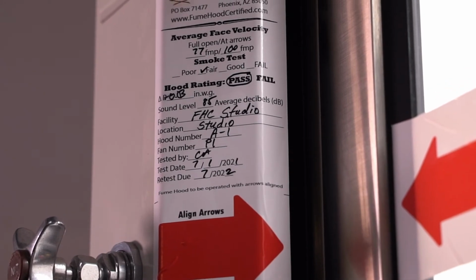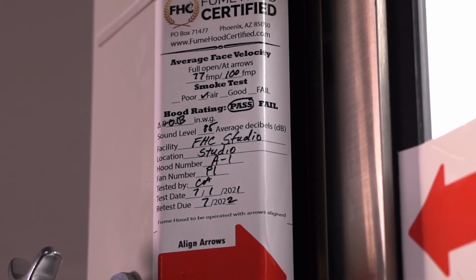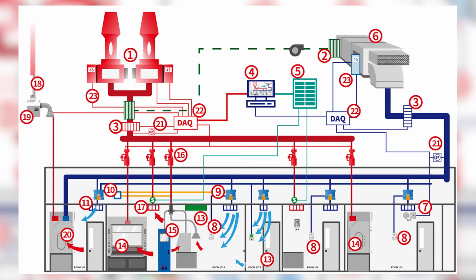Like most safety equipment, there should be a regular checkup for the fume hood, at least annually, and ideally twice a year. A trained inspector can spot many problems that can be addressed, often easy fixes. Then there are self-audits that the user and the lab manager can do. Internal EHS and facilities people can perform various types of testing, and when problems are suspected, an outside tester or troubleshooter can be brought in. You shouldn't work at a hood that doesn't have a current certification sticker on it. And remember that the hood is also part of a large mechanical system that requires regular calibration and maintenance.